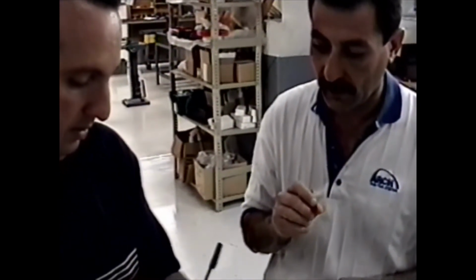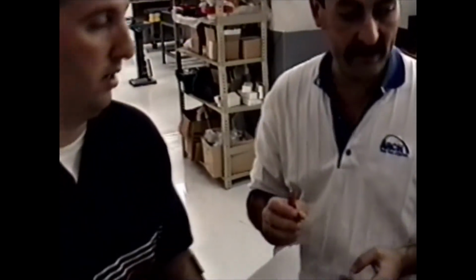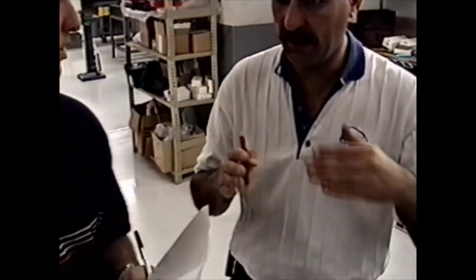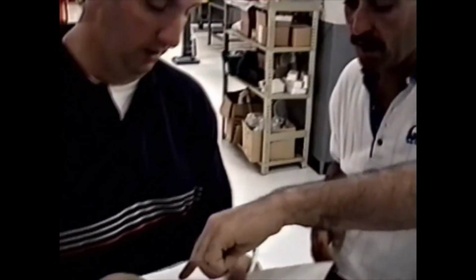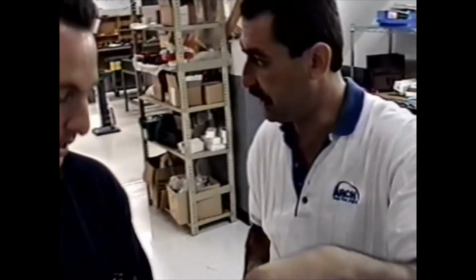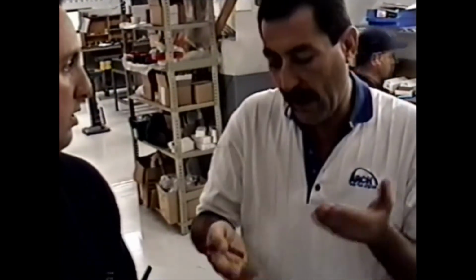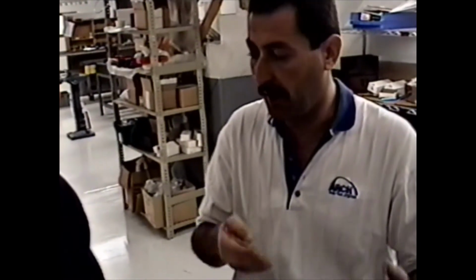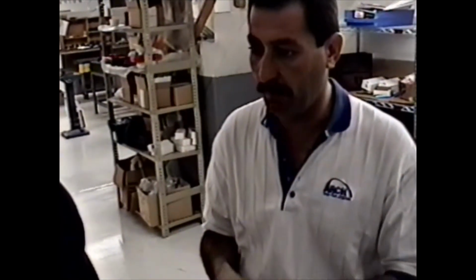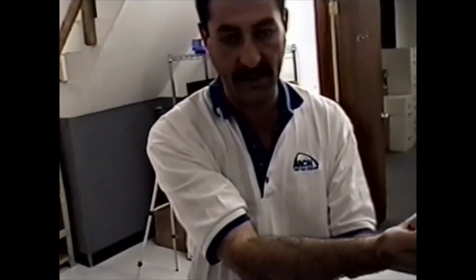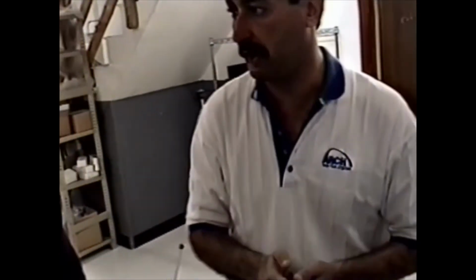Okay? But until both of them read exactly the number that you selected or you calculated, within, I mean, if it fluctuates by 5 or 10, or the difference is 5 or 10, it's okay. But it shouldn't be more than 20 torr difference between this guy and this guy, and that's what you should do. Okay?